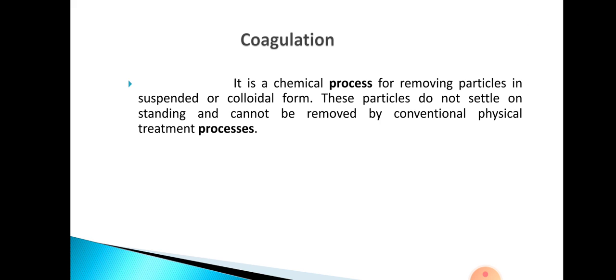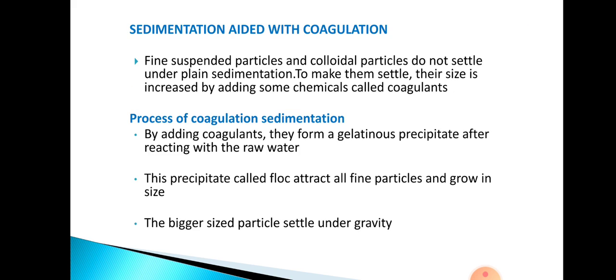So in this case, we adopt the process which we call sedimentation with coagulation. Coagulation is the process wherein we add a chemical to the water, and this chemical will react and form what we call a floc. This floc formed after the addition of coagulant will attract the fine particles, that is the clay particles, emulsions, gels, or other colloidal particles, and as it attracts these finer particles, the size of the floc will increase.